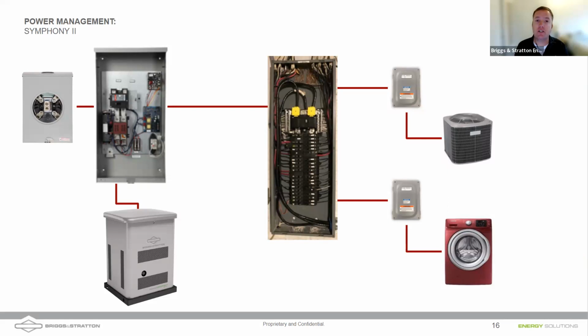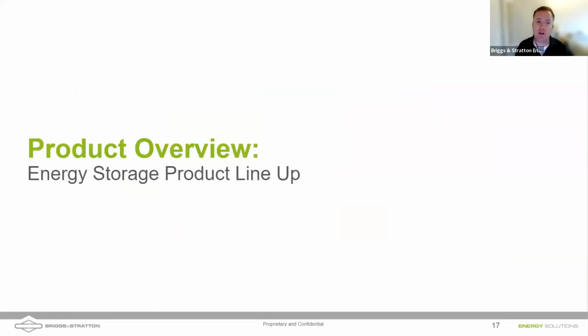One unique solution that we have here is the ability to use our Symphony 2 load shedding devices. These originally were created to drop out heavy loads when you're running on a generator, which allows you to size a smaller generator than you otherwise would have to have. These load shed devices can set priority, where it will drop out as the load on the generator starts to increase. But additionally, you can set these modules to essentially drop out as soon as it detects the generator starting. And what we can do then is drop off solar when a generator starts, avoiding the chances of the solar backfeeding into the generator.